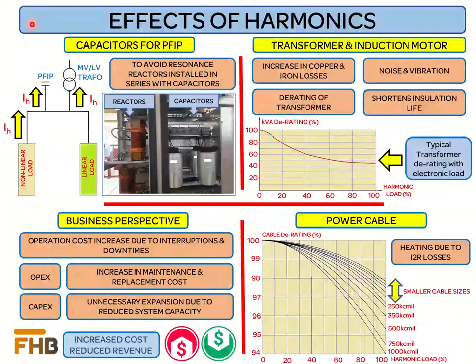For discussion, we have considered the power components which are part of every electrical installation. First, we will discuss the effect of harmonics on capacitors which are connected in parallel with the power system for power factor improvement. The main effects of harmonics on capacitors include heating and dielectric stress, as it acts like a sink to the unfiltered harmonic current, and this shortens the capacitor life.